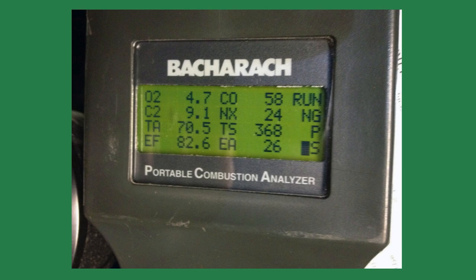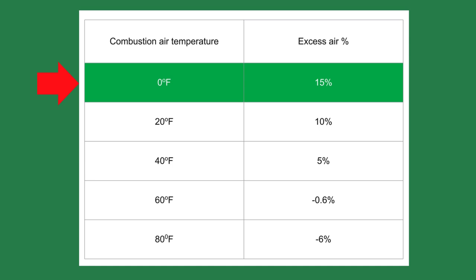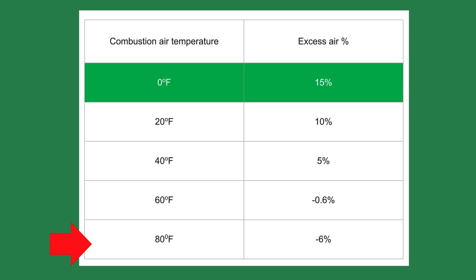We adjust the air to fuel ratio on the coldest days because the loop heats slower and cools quicker. Consider this scenario: it's a cold day, around zero degrees Fahrenheit, and we set the boiler and burner for 15 percent excess air or 3 percent oxygen. When the outside air temperature rises to 40 degrees, the excess air drops to 4.6 percent or 1 percent oxygen — perilously close to sooting. At 60 degrees, the excess air is negative 0.6 percent — we are definitely sooting. At 80 degrees outside, the burner is operating at negative 5.8 percent excess air — a real mess.